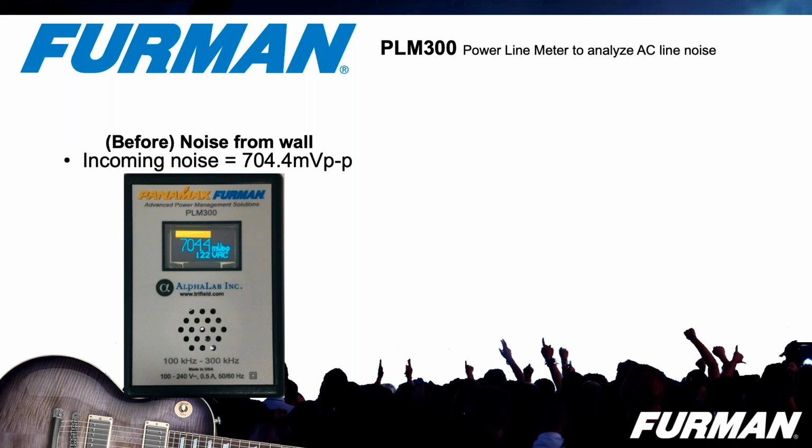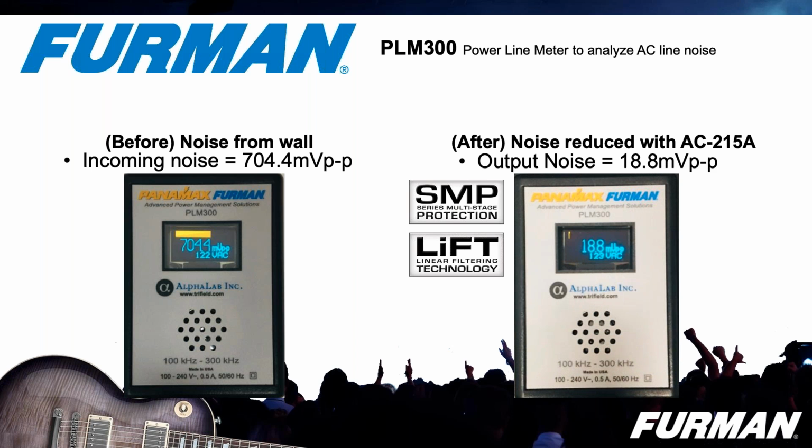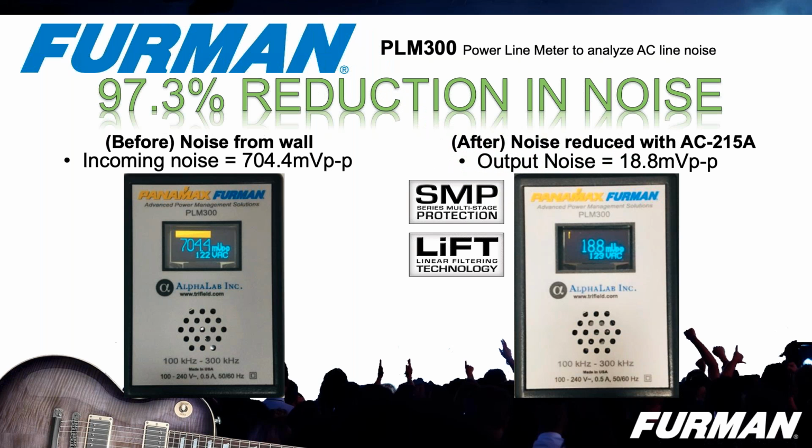So with that, we took something with our SMP LiFT technology, because those two actually work together. LiFT helps to reduce that noise, as well as the SMP for those spikes and surges, and then the LiFT will reduce that EMI and RFI at low levels. What we found by measuring afterwards is we went down from 704 millivolts to 18.8 millivolts on the output. That turns into a much quieter background, and as far as numbers go, that's literally a 97% reduction in the noise. And this was just using something as simple as our little AC215A. But anytime you see SMP, that's always going to have EVS and LiFT in there as well, so you're going to get these same results from any of our devices that have that.